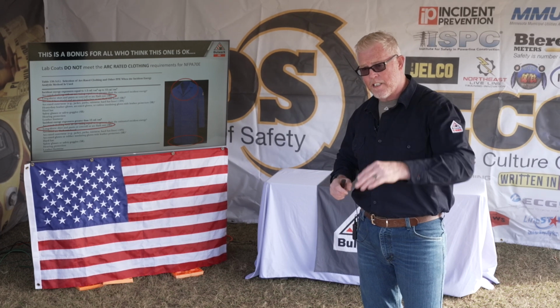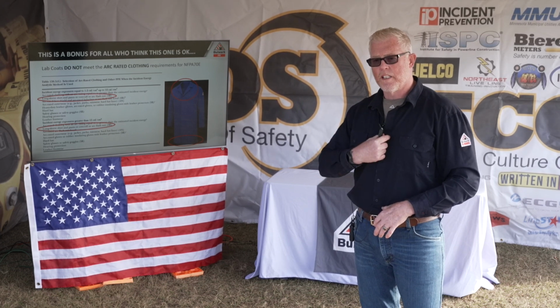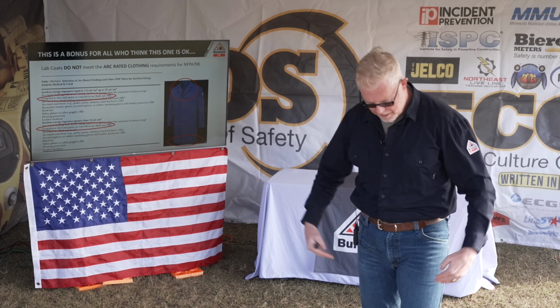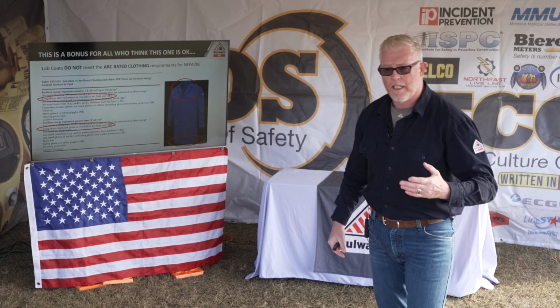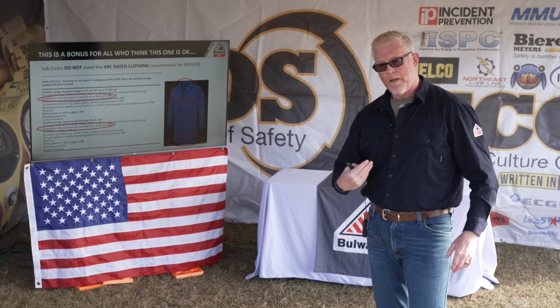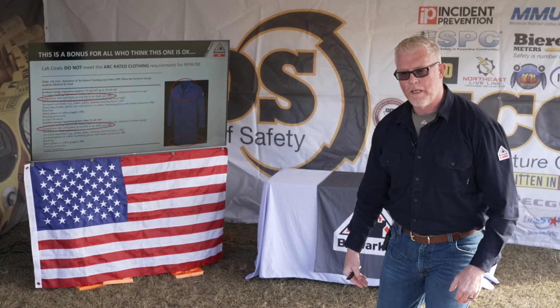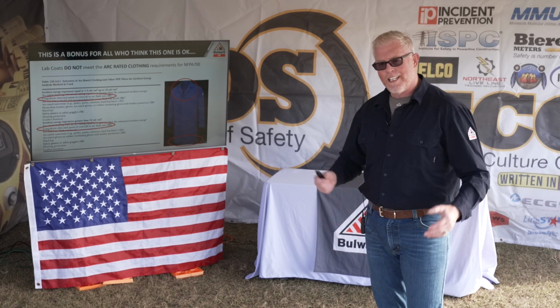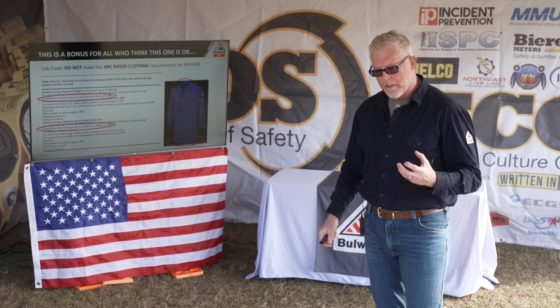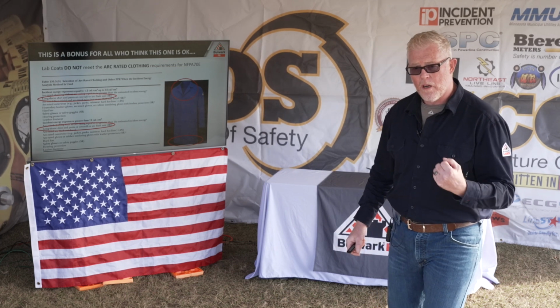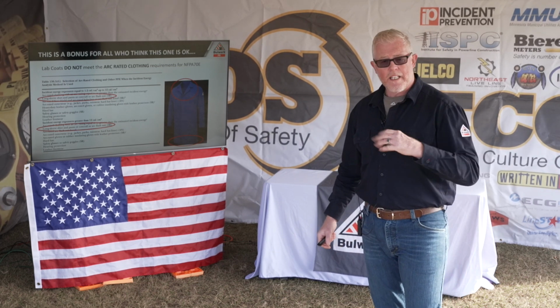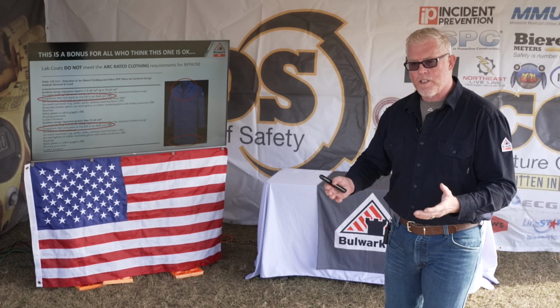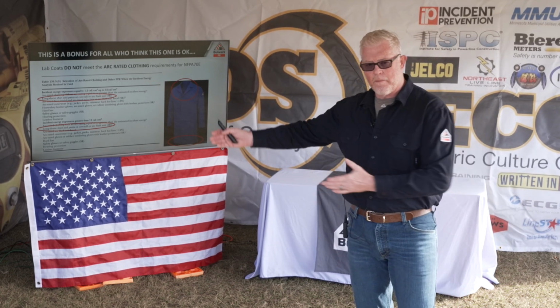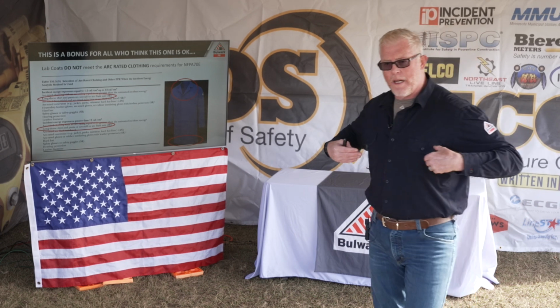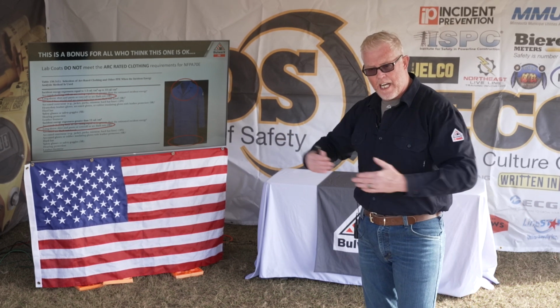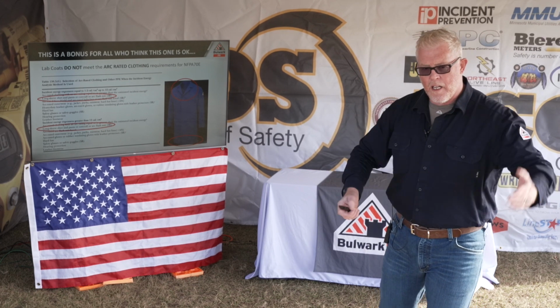Yes, it has long sleeves, but it does not secure up to the neck — there's too wide a neck opening. Everything below is exposed for the arc to hit the ground and come back up, and also for potential fuel being worn from the waist down. We do not want to see lab coats used as a primary protector, or even supplementally, and definitely not as a guest option for when you need flame-resistant arc-rated clothing moving through the facility. So I come in my business suit, take off my jacket, and now you're going to give me a tour and put this on me? Definitely a no-go.